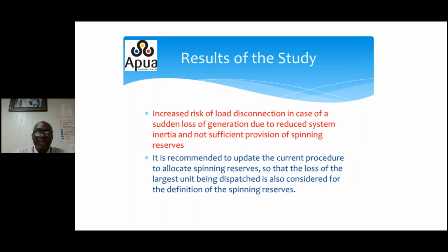Another concern that IRENA had with the grid, they've indicated increased risk of load disconnection in case of a sudden loss of generation due to reduced inertia. Now, we know that the fossil fuel plants offer a lot more inertia to the system. And high inertia means more stability. So you basically want a situation that when the fossil fuel generators are off, you will have enough inertia on the system to maintain stability. The recommendation from IRENA is to update the current procedure to allocate spinning reserve so that with the loss of the largest unit, you don't have a major issue.